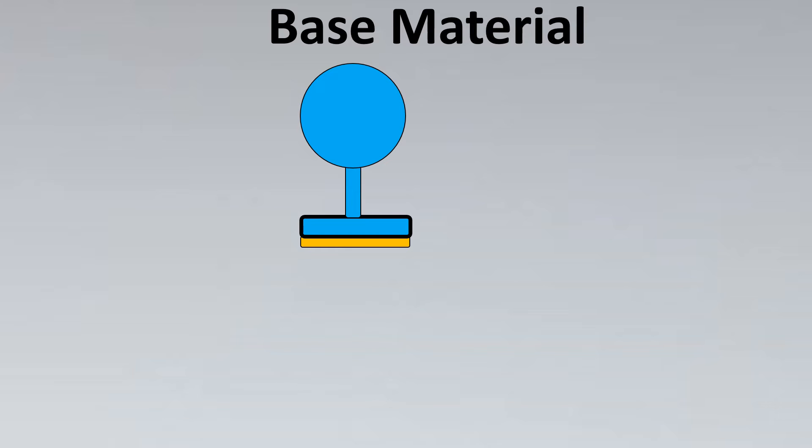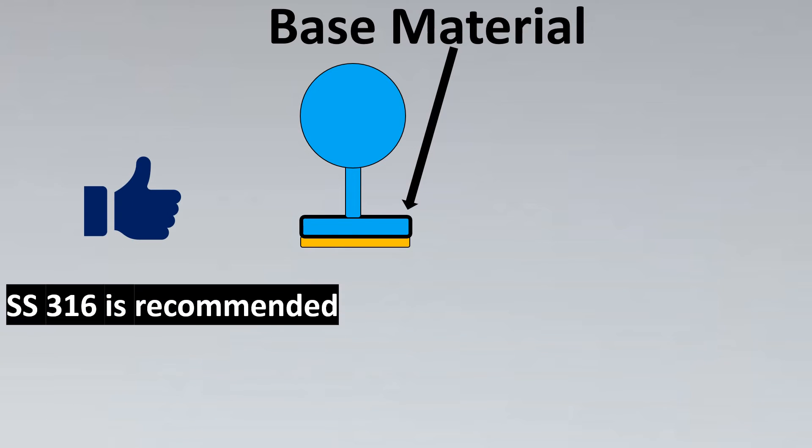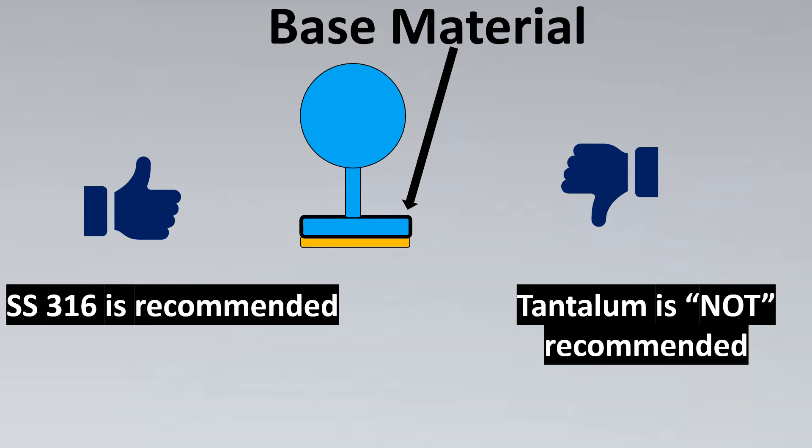For such cases, API standard specially recommends SS316 material. This base material usually is recommended to be SS316, and below it would be our gold plating. What is the least recommended one? It's tantalum, because it is the least recommended when it comes to hydrogen service. This metal is not suitable for hydrogen services. If your gold plating fails, this material is going to be exposed to the service, which is absolutely not recommended.